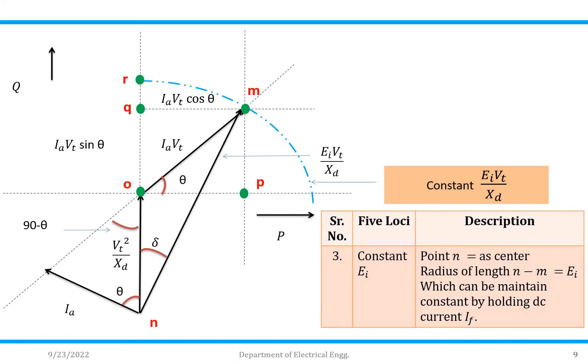The third locus is constant EI·VT/Xd. Take N as the center and NM as the radius. Drawing the curve with this radius gives us the locus for constant EI·VT/Xd. The radius NM equals EI·VT/Xd, which can be maintained constant by holding the DC field current constant. If your generator operates within this region, it will be operated within a safe limit. This is the limit called constant EI.